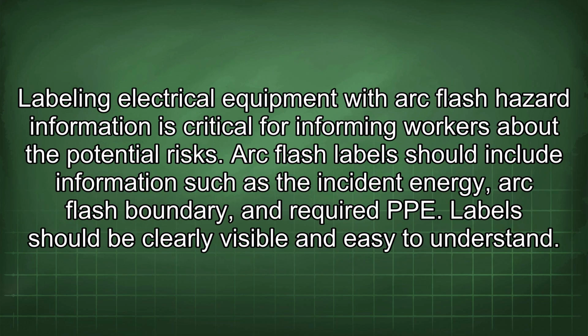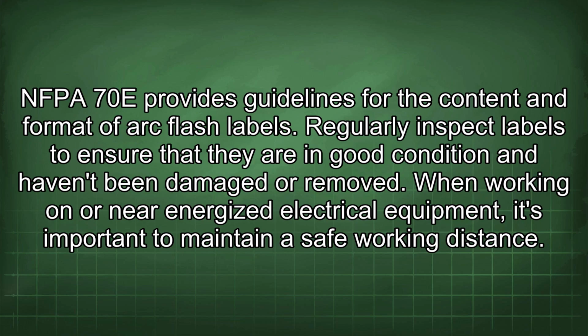Labeling electrical equipment with arc flash hazard information is critical for informing workers about the potential risks. Arc flash labels should include information such as the incident energy, arc flash boundary, and required PPE. Labels should be clearly visible and easy to understand. NFPA 70E provides guidelines for the content and format of arc flash labels. Regularly inspect labels to ensure that they are in good condition and haven't been damaged or removed.